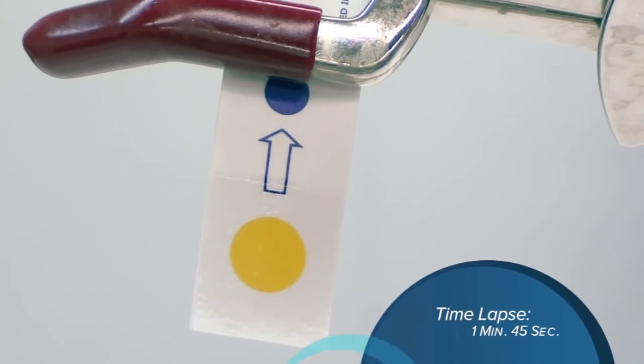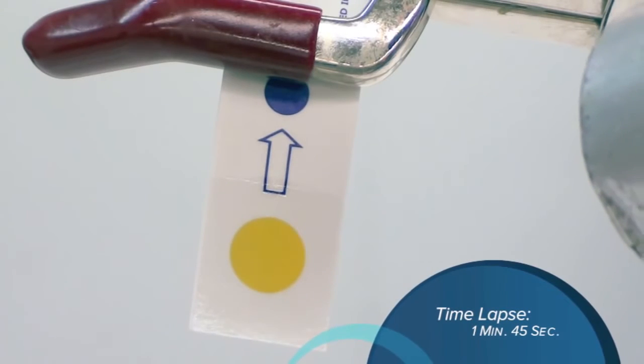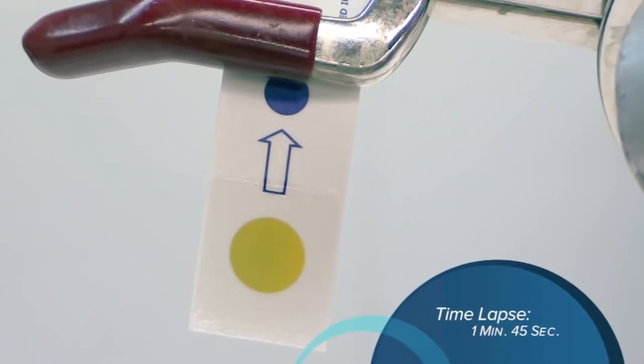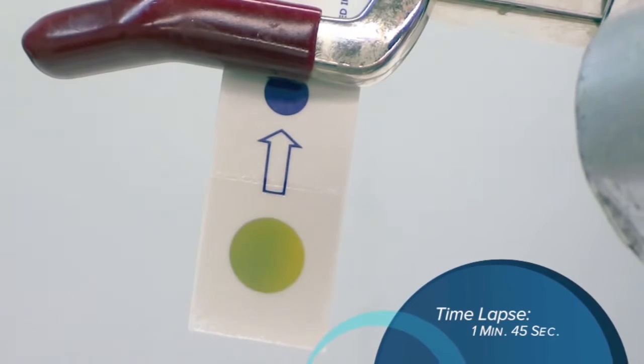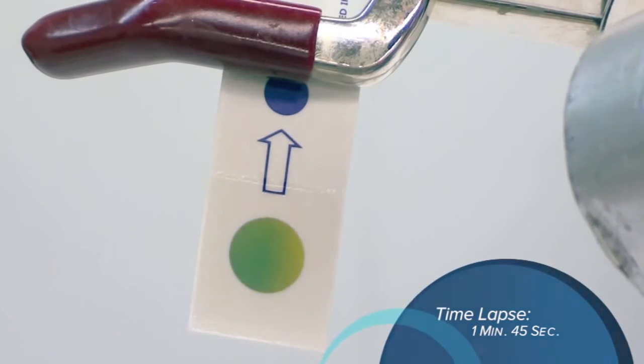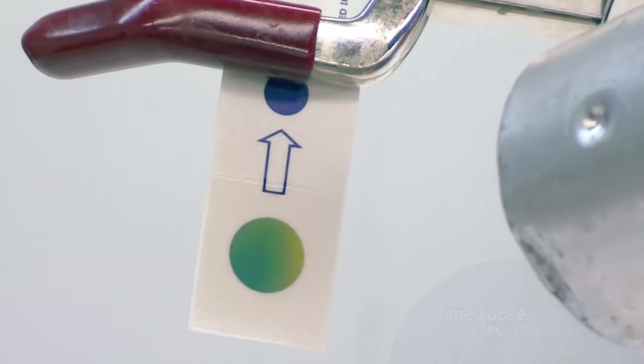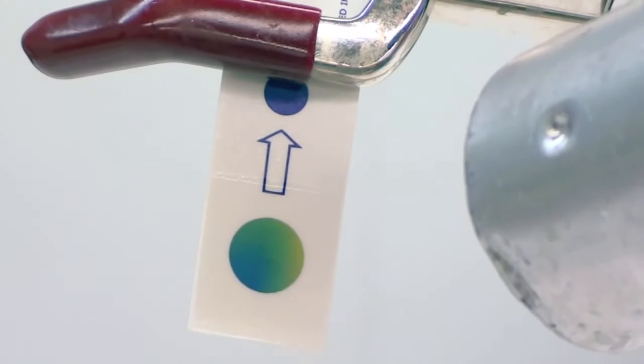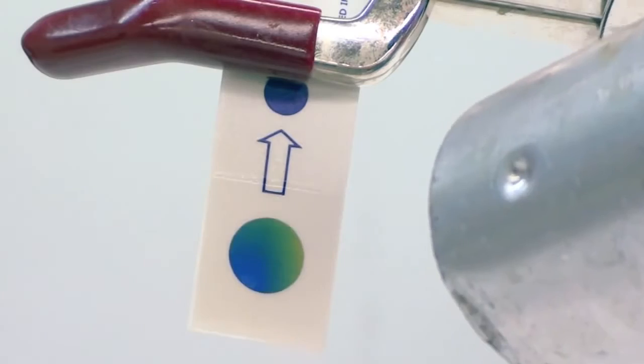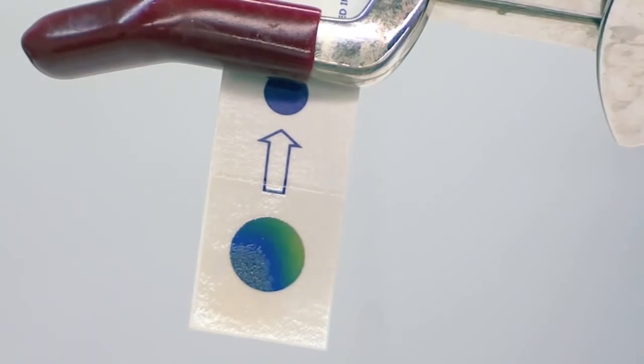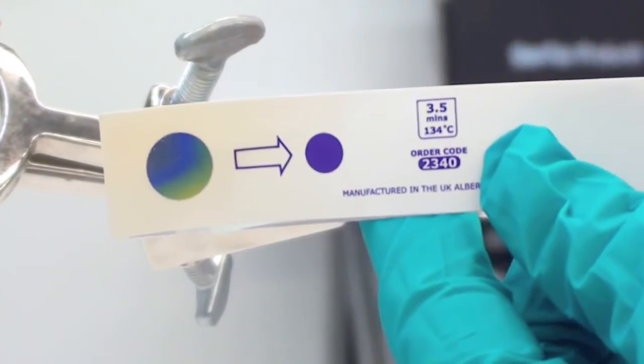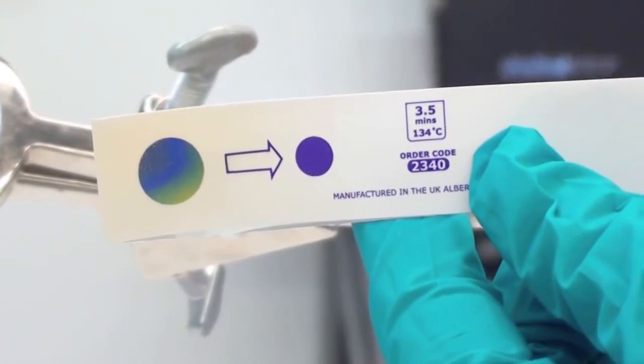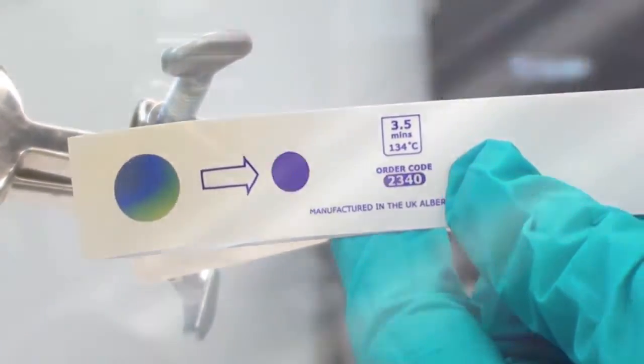As you can see, the prescribed yellow to blue color change occurs without any steam being present after only 1 minute and 45 seconds of dry heat exposure. If this were to happen in a real-world scenario where a load could possibly be placed in an autoclave to be processed, but accidentally not started, the possibility exists that enough dry heat could accumulate in the autoclave to change the product to a pass result, leaving the instruments unsterilized with indicators that say otherwise, therefore increasing the risk to the patient.